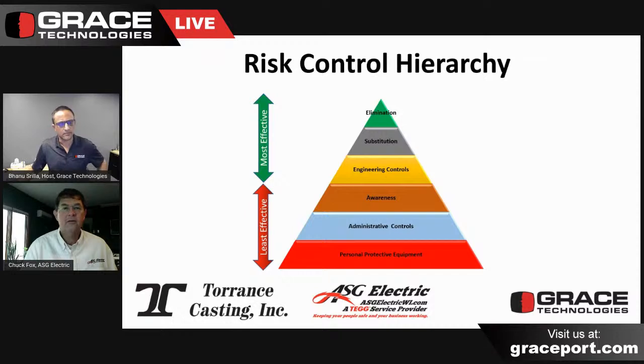The highest level of that hierarchy is elimination. With this particular solution, we've eliminated the exposure to the worker because we brought in absence of voltage devices. As we go down through these different methodologies, the amount of human interaction increases. So as we go down through the hierarchy, we get less and less control, requiring more and more correct interaction from the human side to handle that level of risk assessment and risk control.